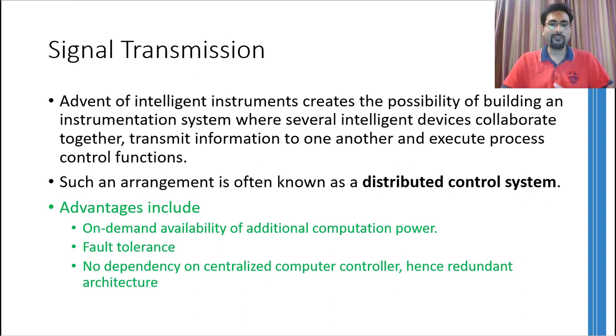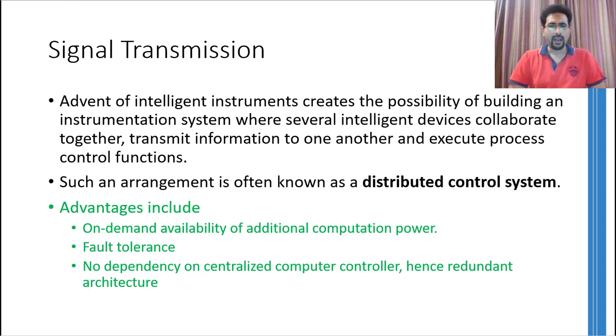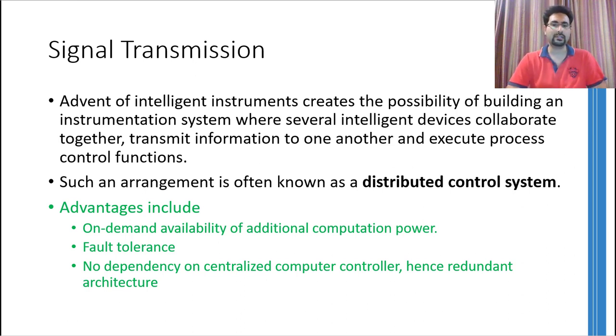Because the whole system is distributed and individual instruments are not fully dependent on other instruments, adding or removing some of the instruments is not a problem. If any instrument fails, the whole system will keep on working. This is called fault tolerance — the system can tolerate certain types and magnitude of faults and keep working even if some instrument has malfunctioned. There is no centralized computer control, so dependency on some central processor is completely gone. These types of systems are called redundant systems.